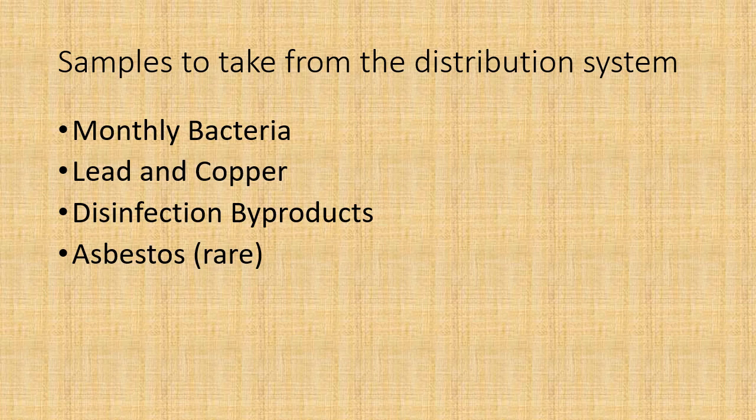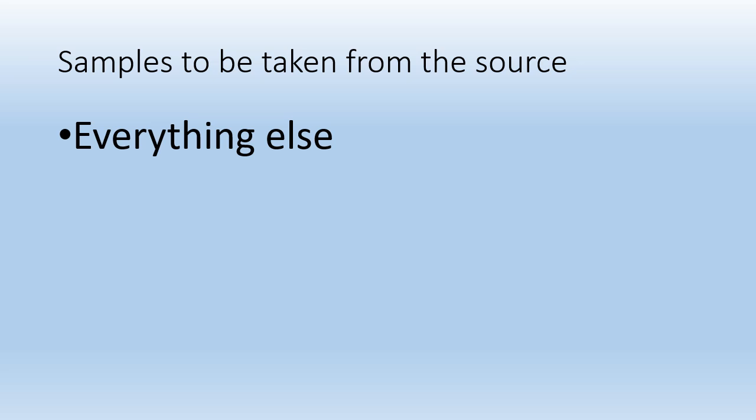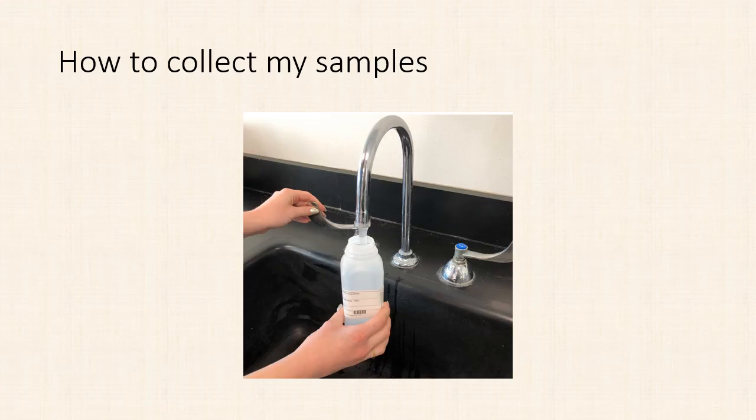Things you need to take from the distribution system include your monthly bacteria from whatever spots are listed on your sampling plan, lead and copper from individuals' homes, disinfection byproducts from a specific place in your distribution system — either the midpoint or the oldest water — and asbestos in rare cases. The source is where you take just about everything else; if it's not one of those mentioned, you take it directly from your source.